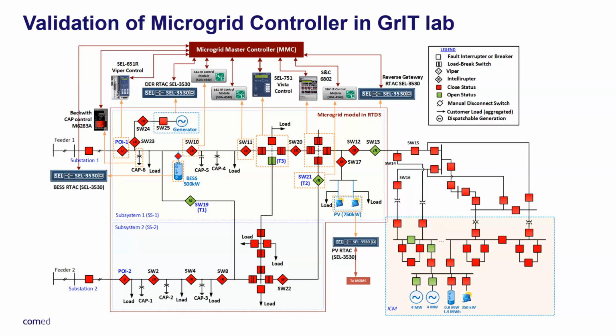In normal operation mode, the two feeders run separately. But if any emergency happens, the microgrid can power itself up, first powering up the upper level feeder by opening up POI 1, and then the generator can power up the feeder while the BESS and PV support the customers.